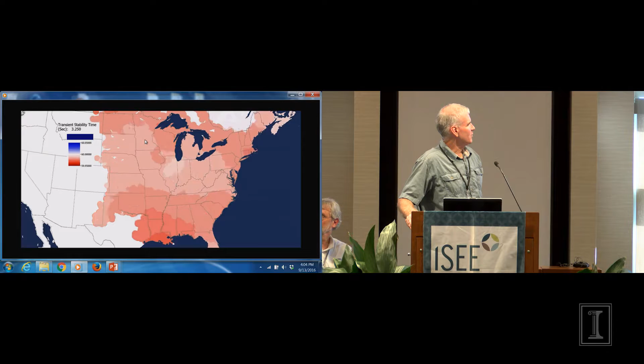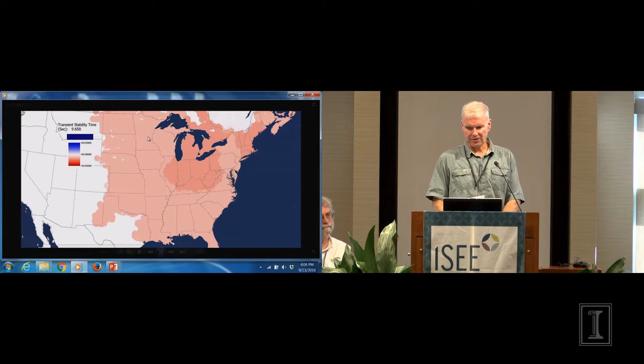We're working on a project looking at the impact of high altitude nuclear weapon explosions, which produce an electromagnetic pulse, or EMP, and what effect that would have on the grid. The effect actually occurs on the same order of time as this simulation. You get a very fast pulse that fries electronics, but then, on the order of seconds to a bit longer than a minute, you get a pulse that affects the grid and causes induced DC currents, which cause problems with our transformers.